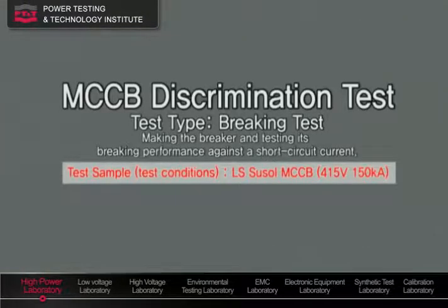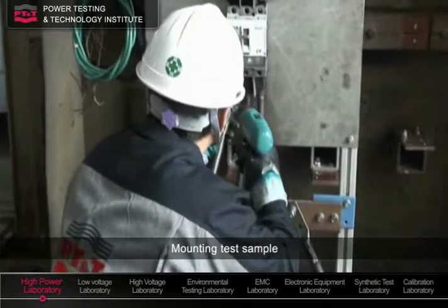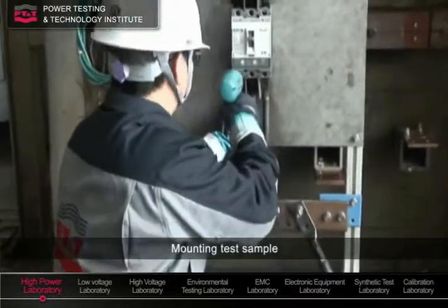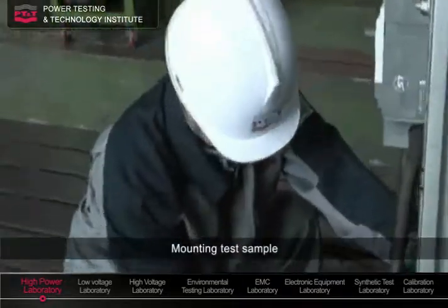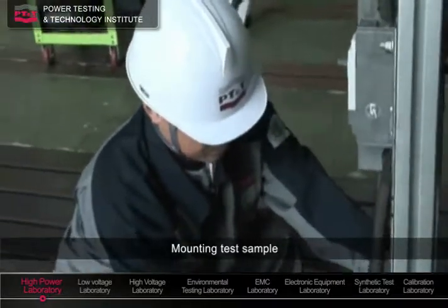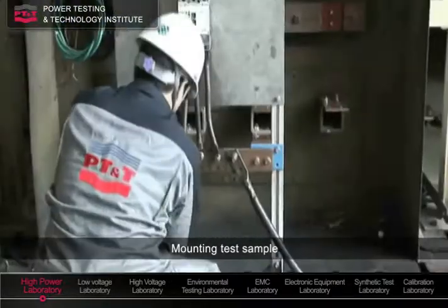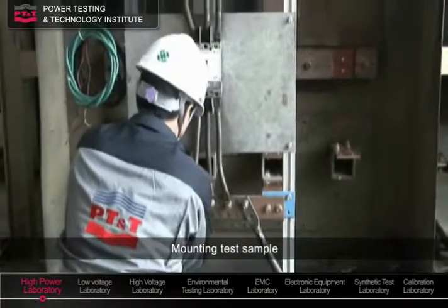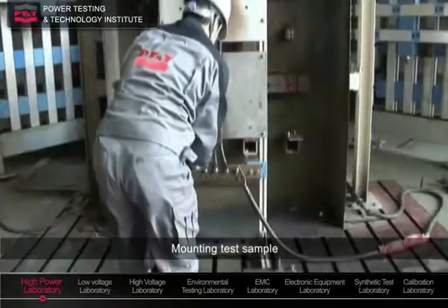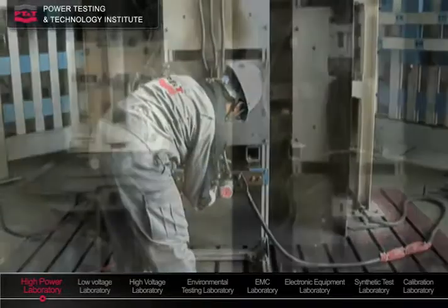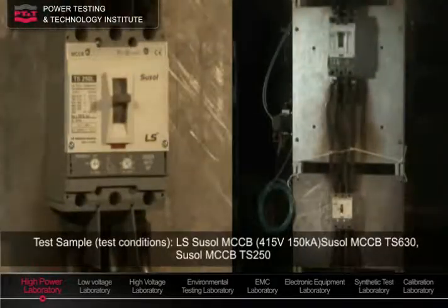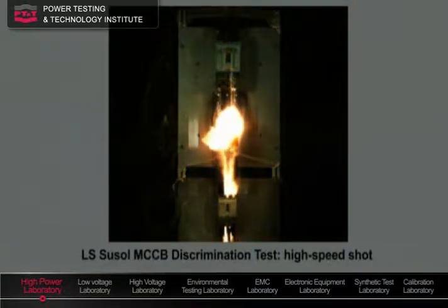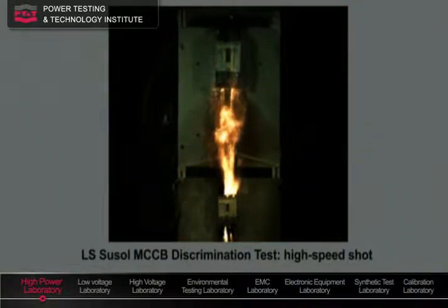This is a successful case of an MCCB discrimination test. Discrimination tests are conducted to verify the backup breaking performance of MCCBs. In this test, only the subbreaker directly related with the fault circuit should be tripped, while the top breaker is not tripped to secure power supply to other healthy circuits. As you can see, only the subbreaker was tripped to prove its reliability and ability of discriminating operation.